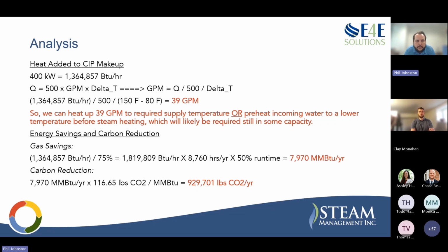But either way, we're able to capture all the heat that was being rejected through the cooling towers, consuming electricity that way. We're instead able to use that heat elsewhere in the facility and save gas and reduce carbon emissions. I did some basic math here. If you have a boiler efficiency of 75%, assume the CIP skid is running 50% of the time year round, that's about 8,000 MMBTU per year, which at the $5 we've been talking about would be quite a bit of money saved. And on the carbon side, that's close to 1 million pounds of CO2 a year. So this would be a terrific heat recovery project if we found it. These are the kind of projects we look for when we go to a site.